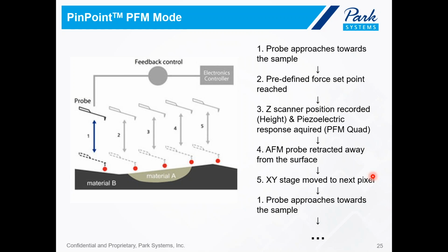No matter whether your sample is very flat or very rough, PinPoint PFM will prevent the tip and sample from scratching. So PinPoint PFM was designed to replace the conventional contact PFM, and it's an enhanced design that eliminates the problem of the tip wearing out during contact mode topography and diminished contact time. The PinPoint PFM technology has proven to solve the majority of the shortcomings of conventional PFM, including quick tip wear, degradation of resolution, poor signal-to-noise ratio, and poor reproducibility.